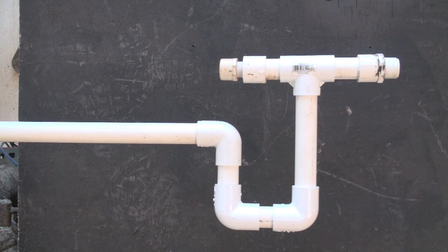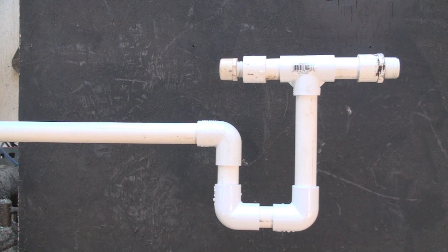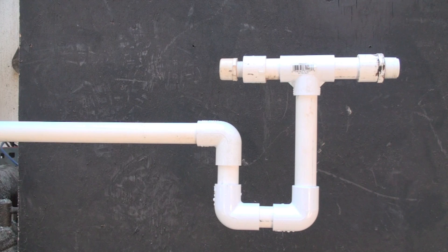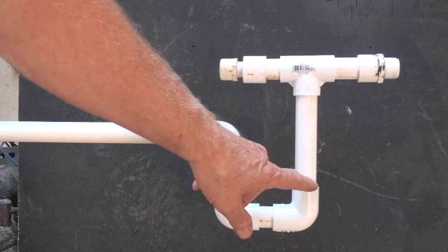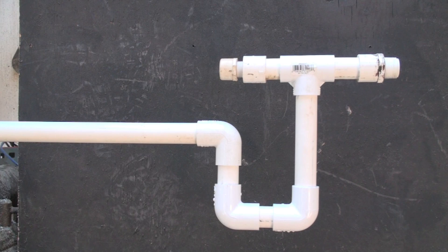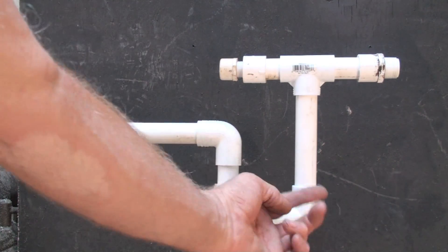This is what I'd call my ideal P-trap. We just looked at the negative pressure that was involved where the condensate drain is. So we can't run it that way without a P-trap because a P-trap is going to have enough weight in the water that's in the trap. This trap here is going to have water up to right about here on either side, and that water is heavy enough that it will not pull air in like this.